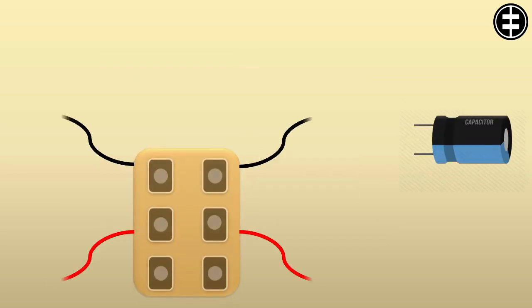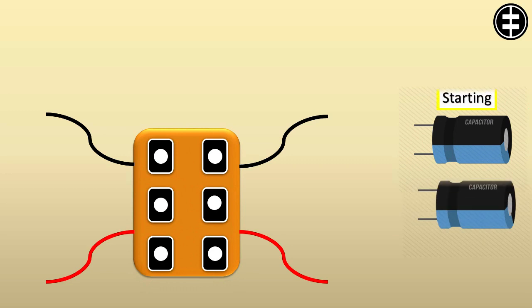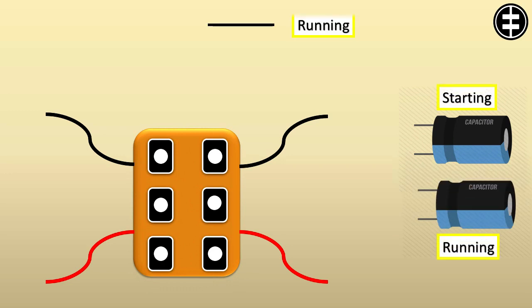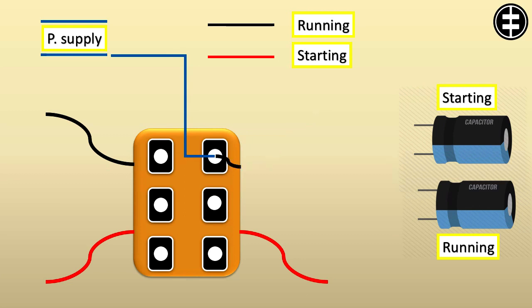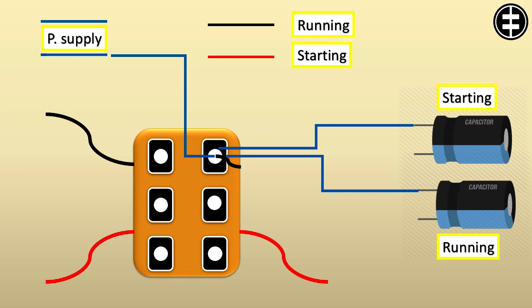Now we can apply the connection. In one point connect one supply lead, one running winding lead, and one lead from each capacitor. The starting capacitor second lead to be connected to the centrifugal switch.